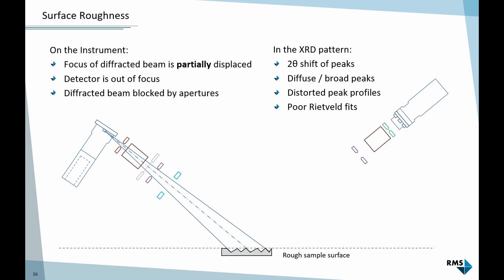The second, sample roughness, is very similar. In this case the sample is centered correctly but the surface is rough. We have surface areas at different levels. Part of the sample will be registered correctly and centered, but the low parts, the holes in the sample surface, will be too low. So we get a blurring of the signal. Parts of the peaks are shifted because of this, parts are centered correctly. We end up with slightly worse resolution, blurred peaks.